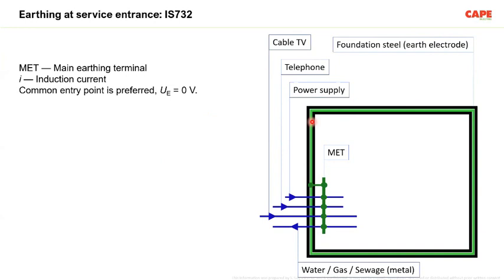The rebar, this green at the center, is nothing but an indication of the rebar. Then you have an MET, and all the incoming metallic services such as power supply, telephone line, cable TV, gas and water are connected to the equipotential bonding system. This is very much necessary. And this bonding system has 3 purposes.